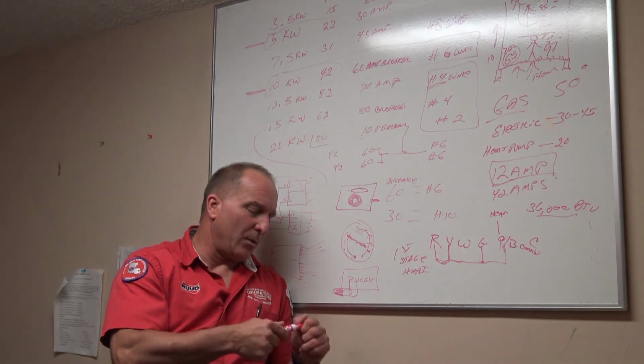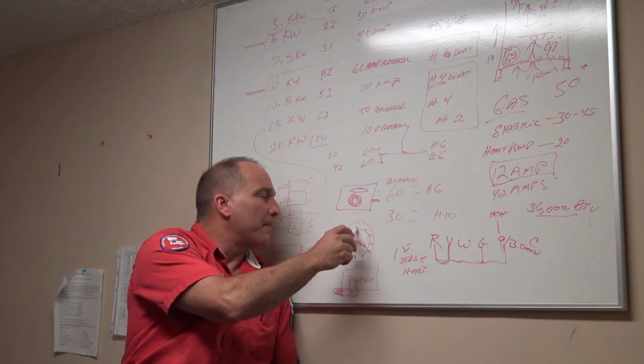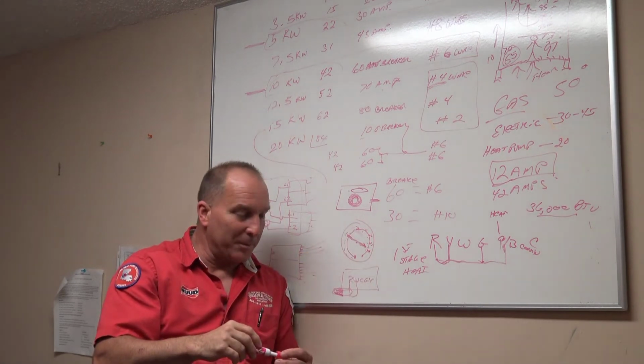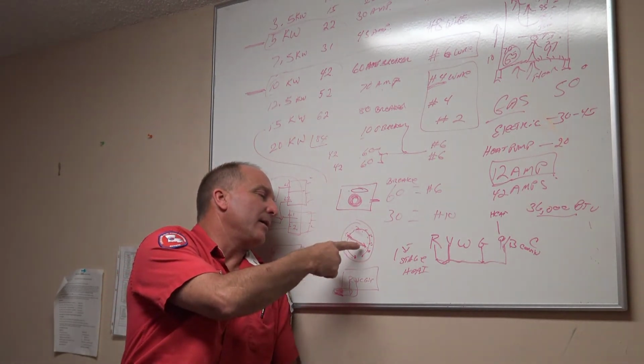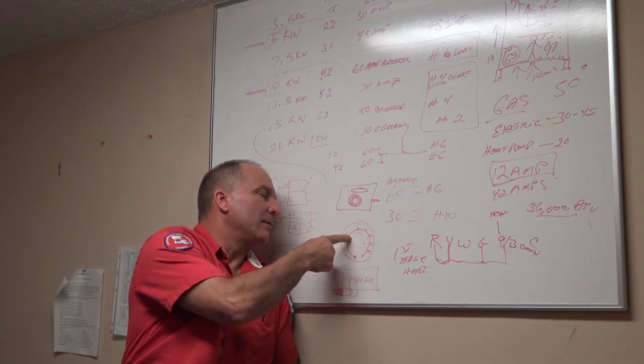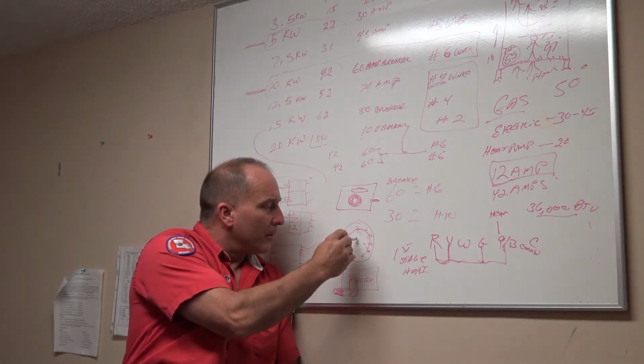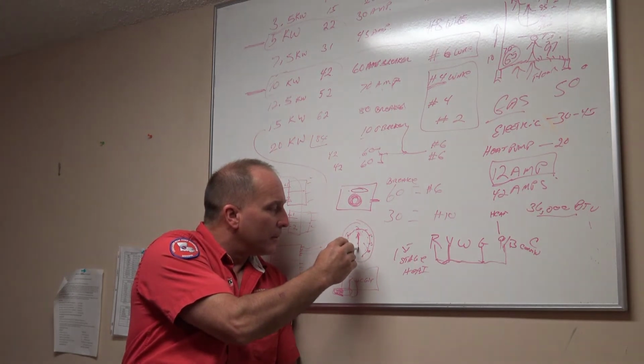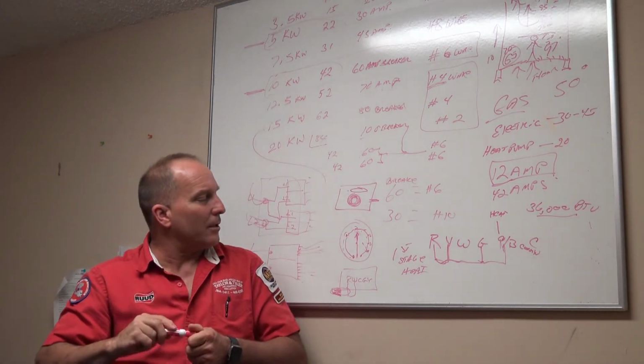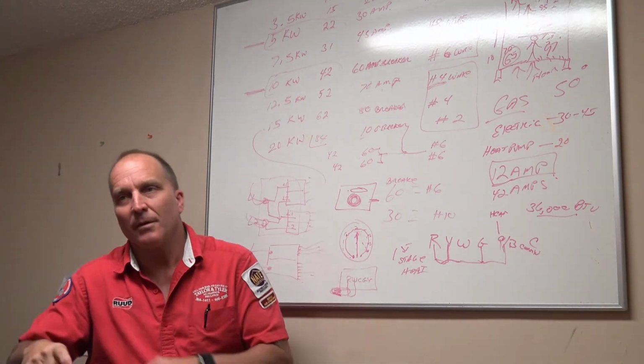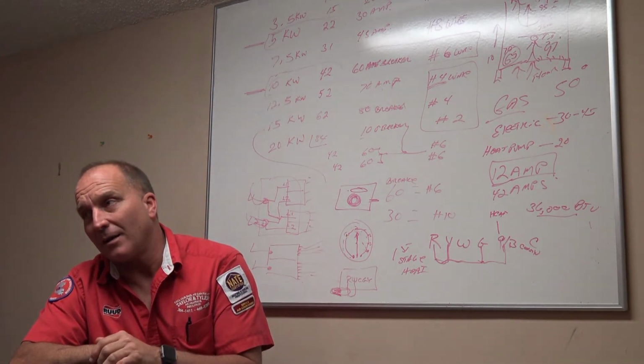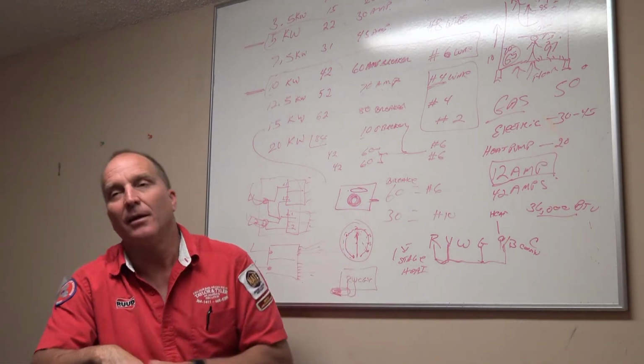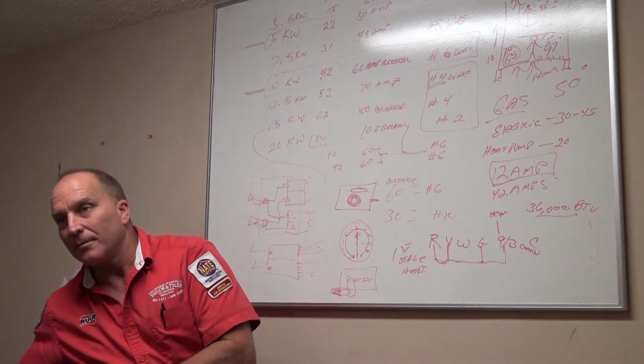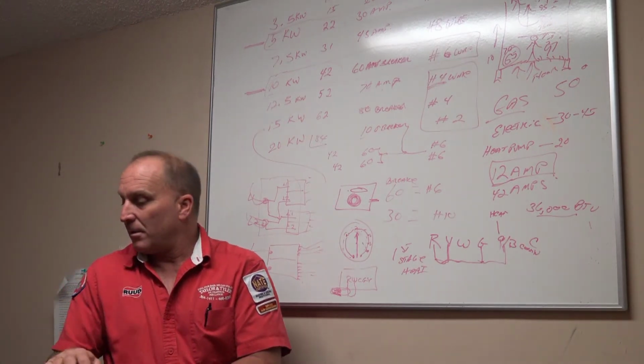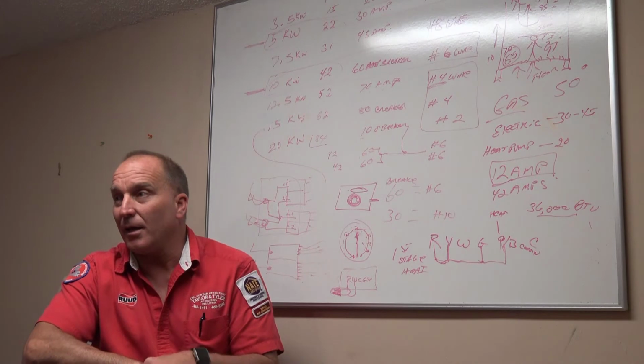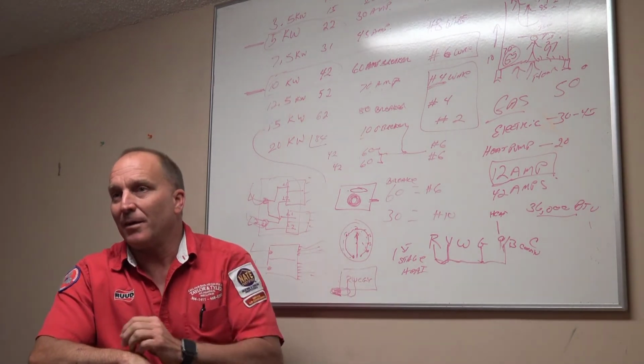Next thing, I'm going to be a real dumbass, and I'm going to say, you know what, I'm going to screw these people over. I'm going to take this little dial right here and turn it, and I'm going to make it now face like this. Now you notice that little arrow is not touching the wire anymore. If I turn that dial, that little arrow does not touch the metal wire around it, and that heater will not come on anymore. So now, you just did your spring check and clean, right? You need me again for the winter time, don't you?